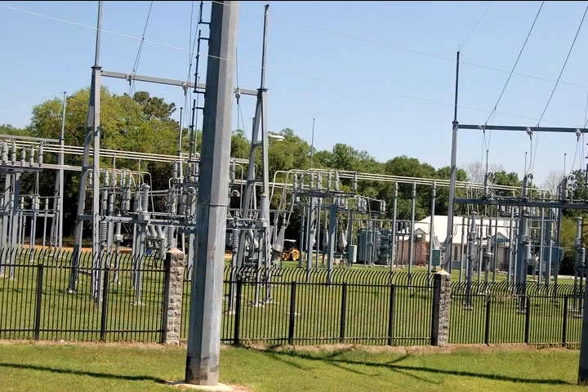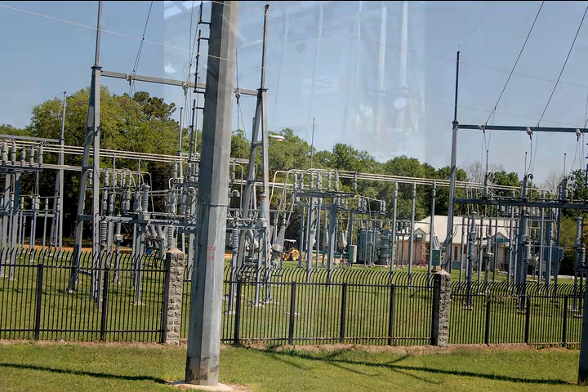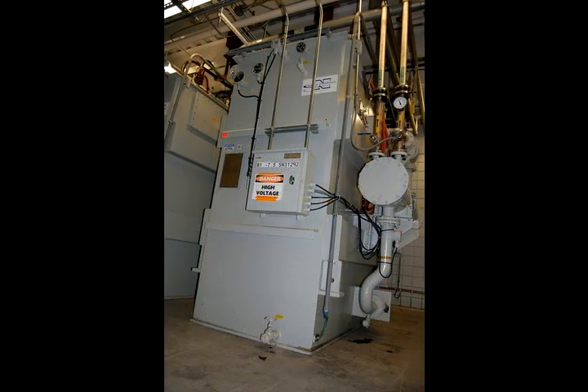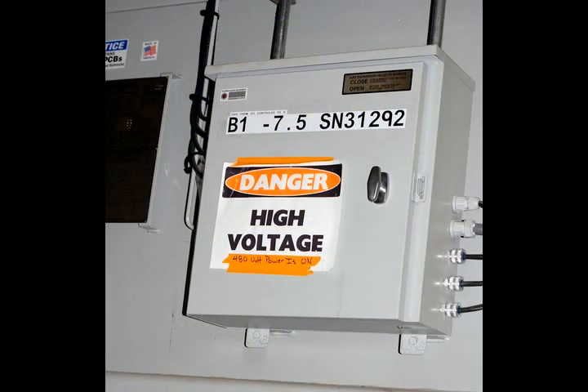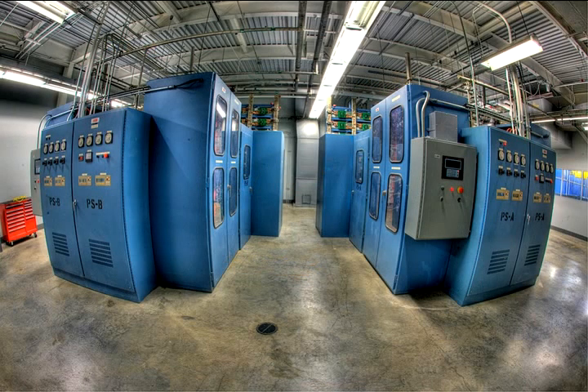Now we use about $7 million of electricity annually. The city has got a 100 megawatt substation. We draw our power from that substation into a series of transformers. They step the power down from 12,500 volts to 720 volts and supply that to our power supplies upstairs where that turns that power from AC power to DC power.